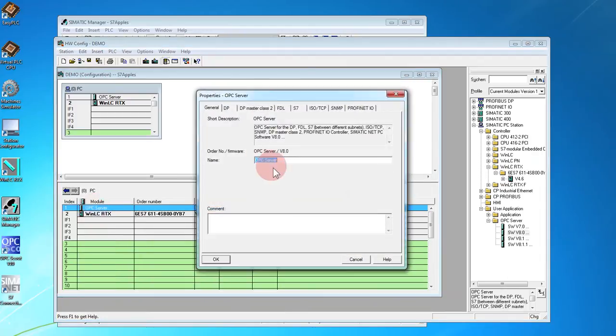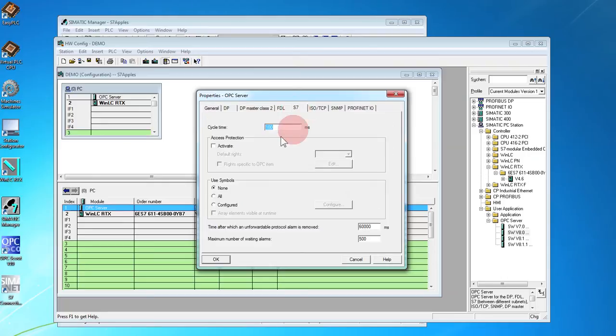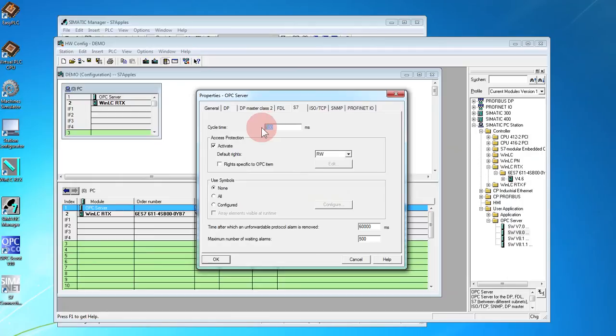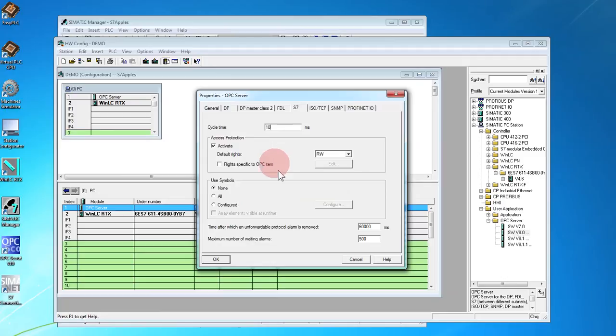Double click to bring up the properties. Go to S7. Activate the access protection and set the cycle time to 10. That's how often the OPC server polls the WinLC CPU and gets the information. We have to set this even though we're going to set up the EasyPLC OPC rate. OK. Save and Compile. Now we can close this.